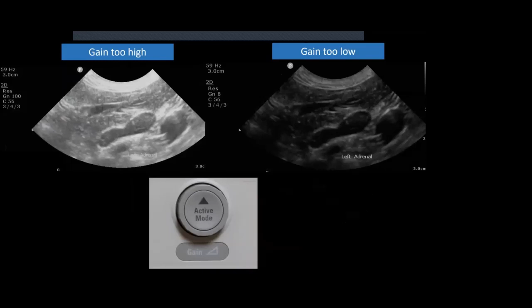And the time gain compensation is simply a gain switch that corresponds to a part of the screen. So this first gain switch corresponds to this part of the screen. This gain switch here corresponds to that part of the screen, and so we go on all the way down. So what you can see in this example here is I've turned the gain down for this portion of the screen, and you can see this dark area as a result of the gain being turned down. And then with this one, we've increased the gain in this portion, and you can see the gain in a band across the image that you can see there. Why is that important? That's important because it allows you to alter the gain at different portions of the screen so that you can even up the image.